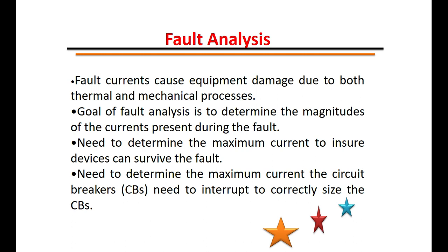Ultimately, the goal of fault analysis is to determine the magnitude of the current present during the fault — what the fault current magnitude is. We need to determine the maximum current to ensure that devices can survive the fault, so that we can take appropriate protective measures. The need for determining fault current is also to determine the maximum current that circuit breakers need to interrupt, in order to correctly size the circuit breakers.